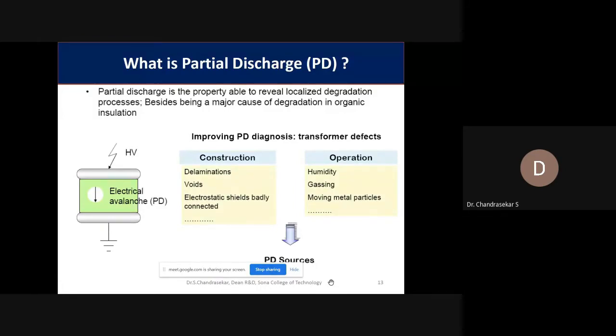A transformer of 5 crores or 6 crores is installed, and suddenly after 6 months or 1 year, due to a bad insulation system inside it, it fails suddenly, and in a fraction of a second, that 6 crores will have gone. So in order to avoid such a failure of such expensive systems, nowadays people are using advanced high voltage sensors. Okay, so that's what we are dealing with: partial discharge sensors.